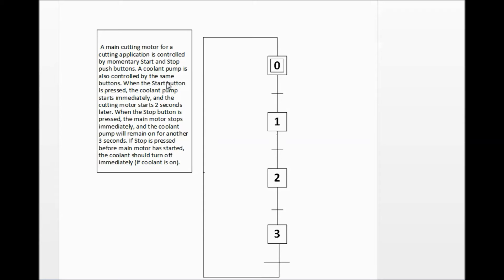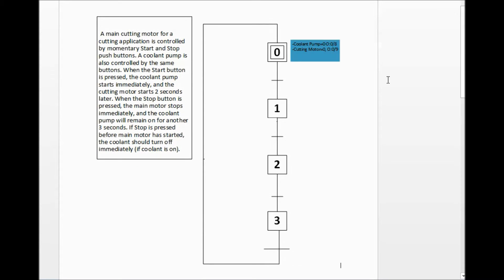When addressing inputs and outputs, always put their actual addresses beside them. We have a coolant pump and a motor, and before anything starts both are off. So at step 0, I'm making sure both outputs are off. Coolant pump equals 0 — low, so it's off — located at O:0/8, which is the physical output wired to the PLC to control that pump. Cutting motor also equals 0, located at O:0/9.